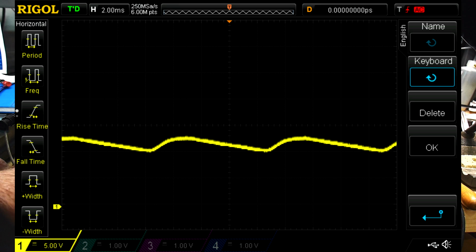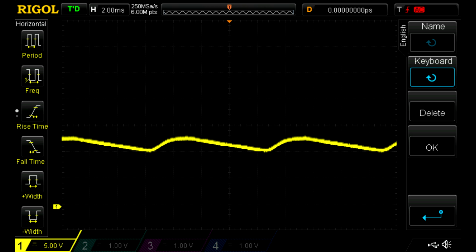When you're building real instruments that go across the world, they end up in places like Japan, which has 100 volts, which lowers the voltage. And it also has 50 hertz, which lowers the voltage because your ripple will increase with 50 hertz.